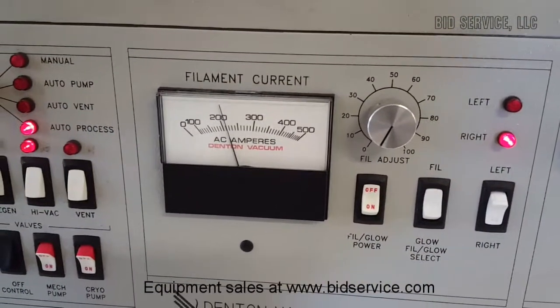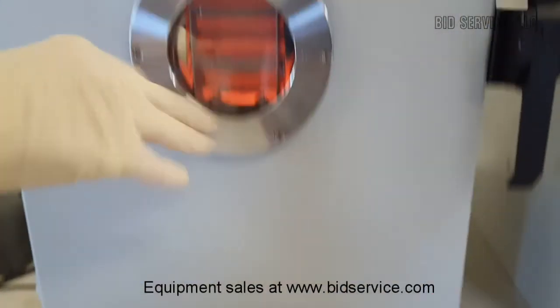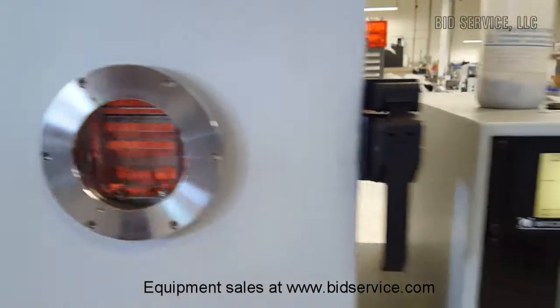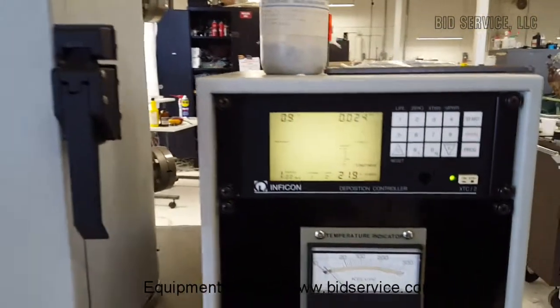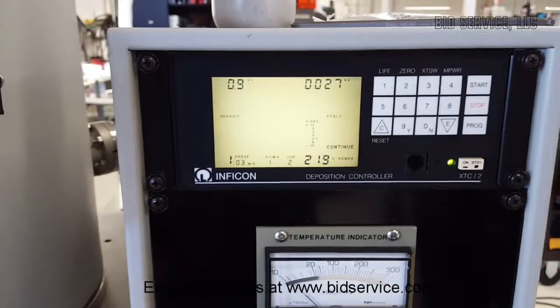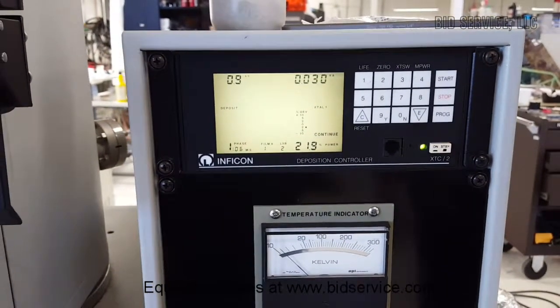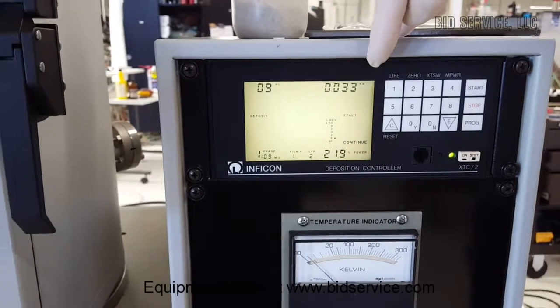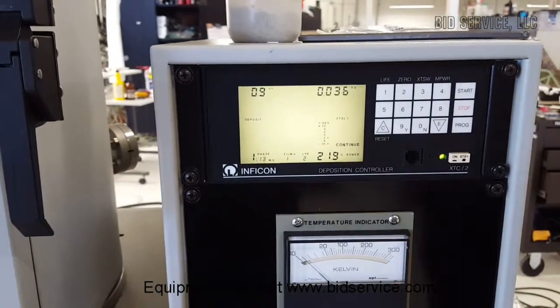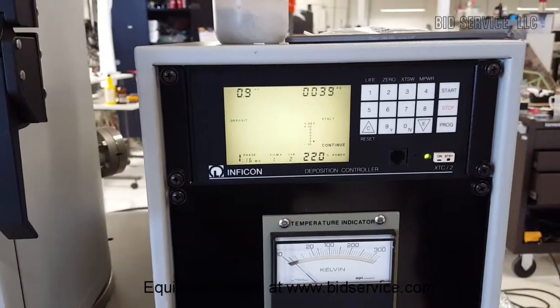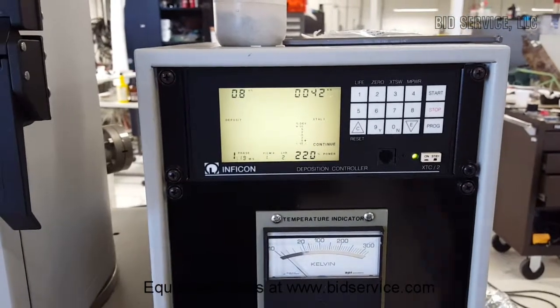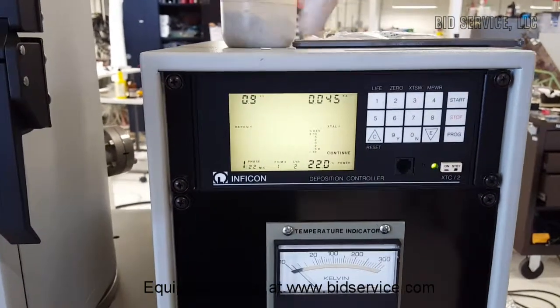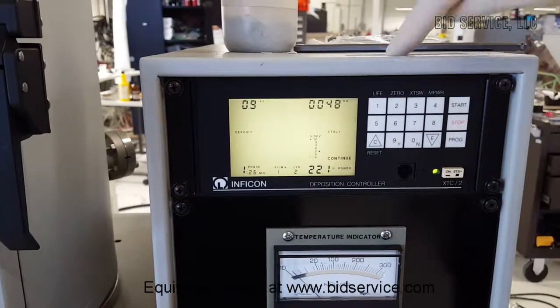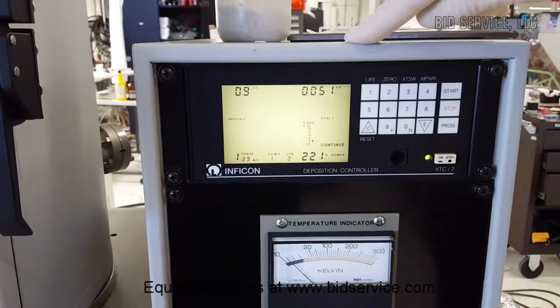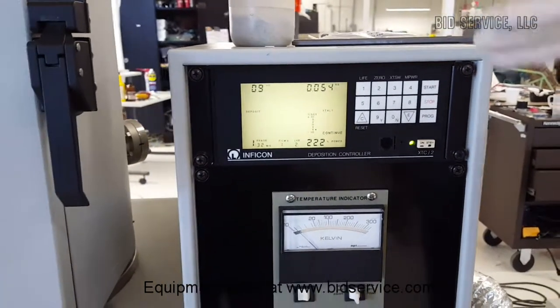Looking down here, you can see the filament current. And looking through the glass, you can see that there's an orange glow inside. Here we're at 22, 21.9, and we're pretty close to 1 angstrom per second. So again, it's going to control here, trying to maintain 1 angstrom per second. It'll adjust the power until we hit the 500 mark, and then it'll shut everything down, close the shutter. So we'll come back in a little while and see how it's going.